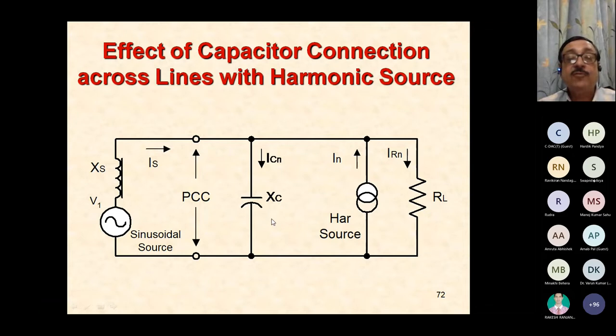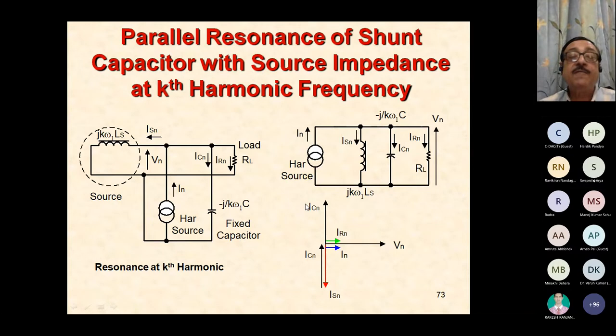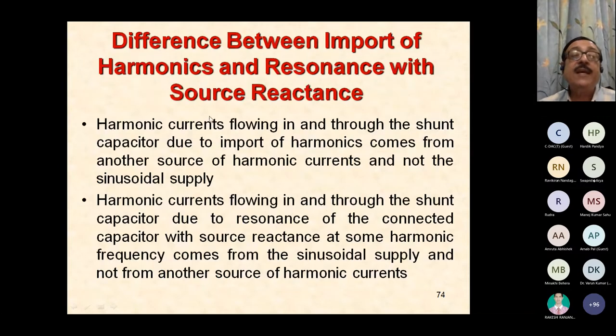And the second thing is the total current through the capacitor is also going to increase. Increased current through the capacitor creates dielectric losses. You have heard something called tan delta in the capacitor. There is a loss, so more current means more losses in the capacitor. Its temperature will rise and it will ultimately fail. So this is what you have to be very careful about. So there are differences between input of harmonics and resonance with source reactances.